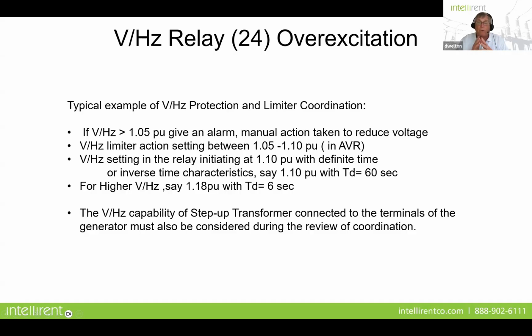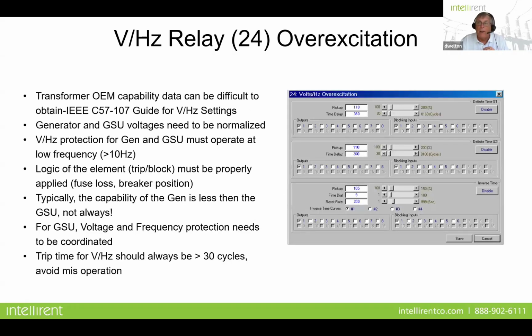But the volts per hertz capability of a step-up transformer connected to the terminals of the generator has to be considered during the review of this coordination. It's got to be very carefully calculated, and your protective relay manual will help you do this. Now, just a couple of guidelines.